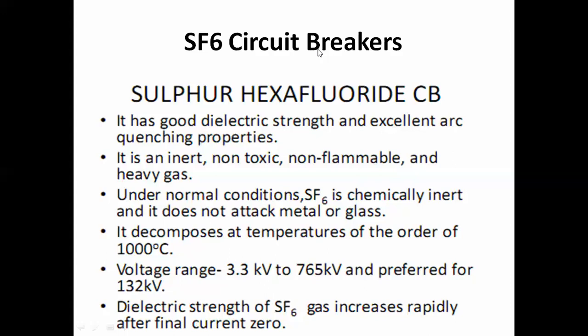So here you can see that this type of circuit breaker is used in generating stations, in grid stations, and in distribution systems. So at any application, at any point, we can use this type of circuit breaker. The dielectric strength of sulfur hexafluoride gas increases rapidly after the current zero. That means it is one of the most important properties of sulfur hexafluoride gas, that its dielectric strength will increase when the current has a value of zero.